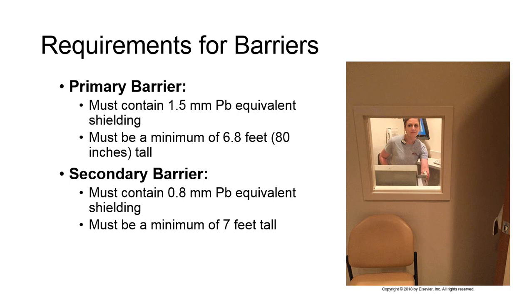In practice, any scatter reaching the operator behind the secondary barrier or the control booth must be scattered at least twice due to these safety regulations, and therefore would be extremely low energy by that point.